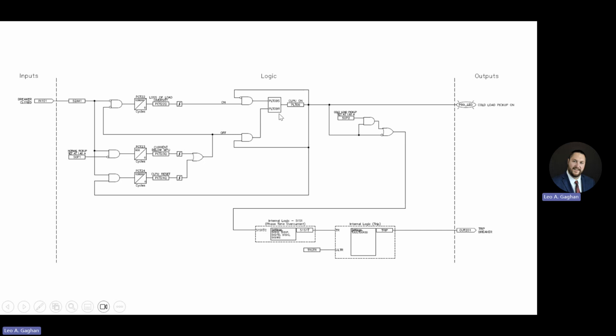It will hit the reset, but that won't do anything because it's already off. And then same thing here, we have a 1 coming here. With the breaker being closed, if this was on, which it's not, you would reset it. But with this being off, that'll be a 0, so it can't do anything. So sorry I had that wrong the first time. But the general thing I wanted to get across there was breaker closed with cold load pickup off, nothing's going to happen.